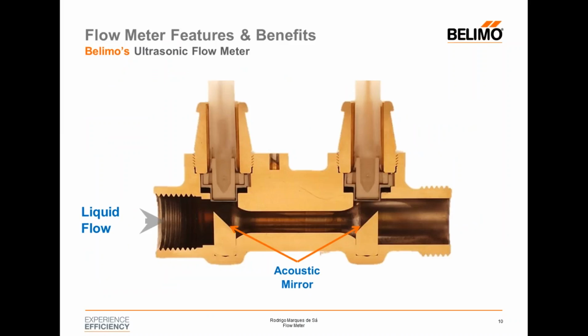Talking about how it works, the flow meter is very simple. It's a transit time solution, an ultrasonic one. We have two acoustic mirrors in the bottom part, and on the left side we have the liquid flow. We also have two emitters and two receivers that we call A and B. We also have a differential feature compared to other suppliers: a temperature sensor.